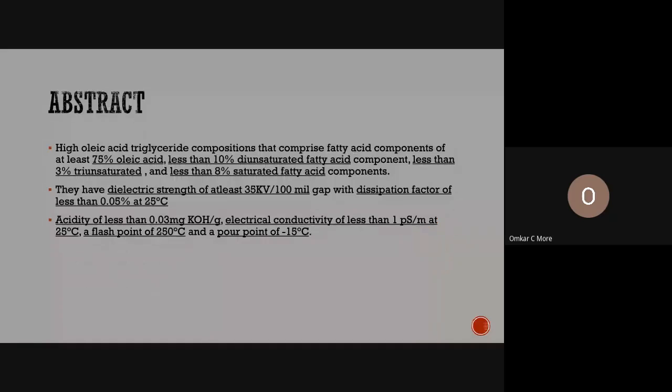As the abstract says, high oleic triglyceride compositions that comprise physical properties as 75% constituent of oleic acid, less than 10% of diunsaturated fatty acids, less than 3% of triunsaturated fatty acid, and less than a few percentages of saturated fatty acids.